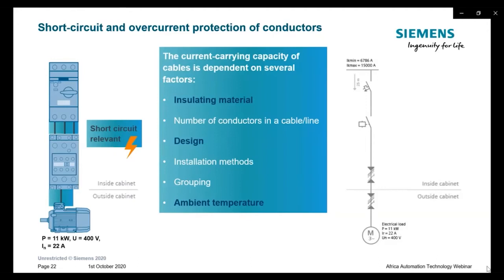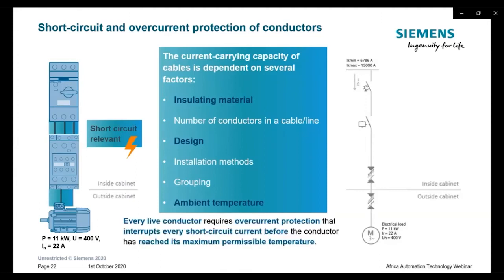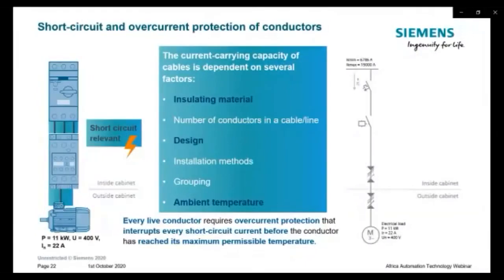For this example, we used an 11 kilowatt drive operated under 400 volts. So nominal current for this one is 22 amps. Every live conductor requires overcurrent protection that interrupts the short circuit current before the conductor has reached its maximum permissible temperature. So the conductor material needs to be designed as per load current, but also overcurrent protection does not exceed its permissible current.